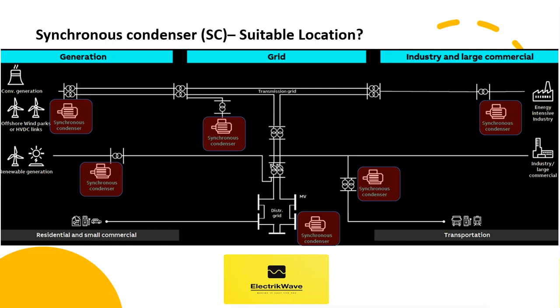In conventional power generation, synchronous condensers mitigate frequency instability that occurs through the imbalance of peak demand and renewable power. They help prevent an increased ROCOF. They also support the grid with inertia and offload reactive power from generators during peak or ramp times, the duck curve. SCs can enable power generation operators to sell additional ancillary services, such as higher inertia, additional fault current and reactive power.